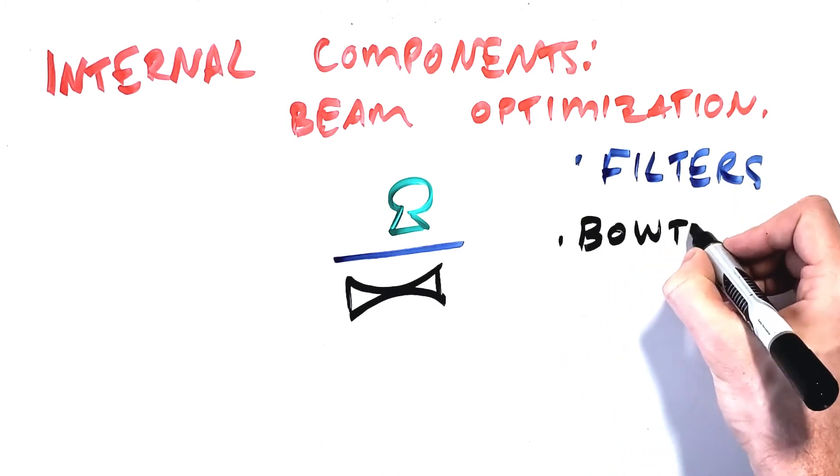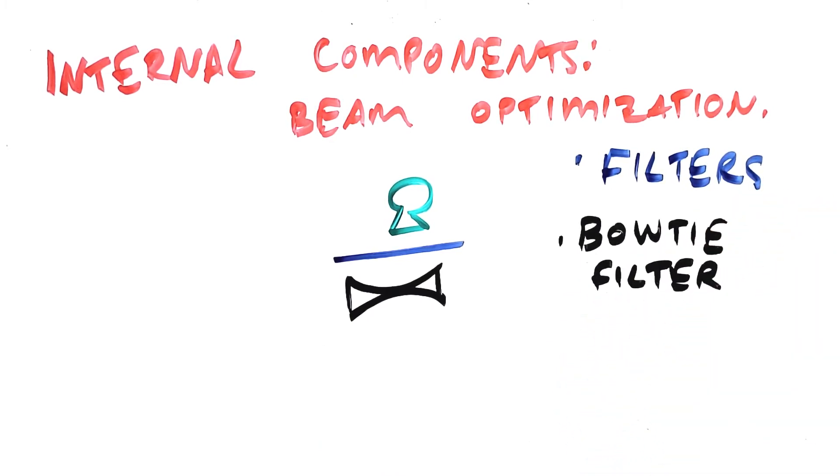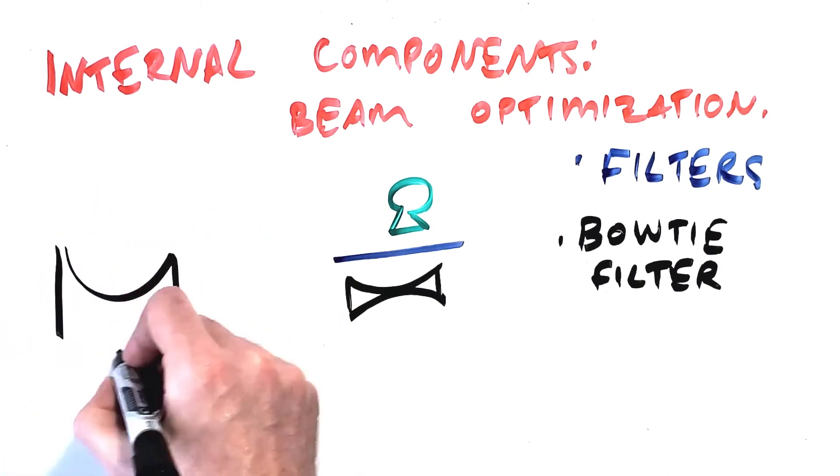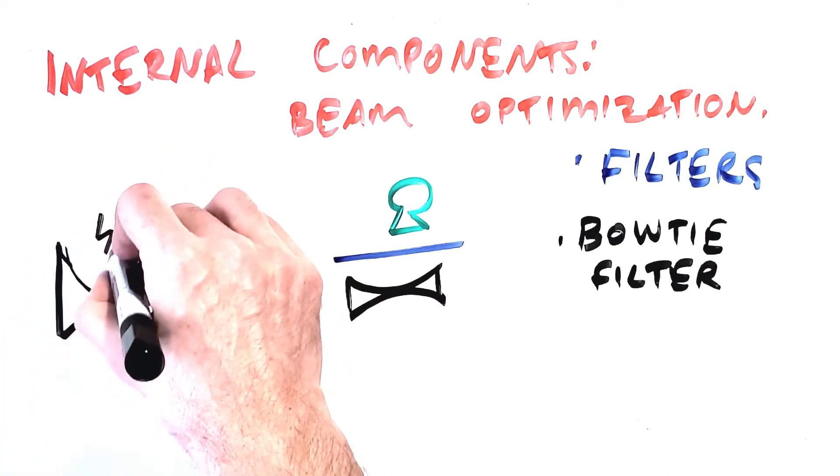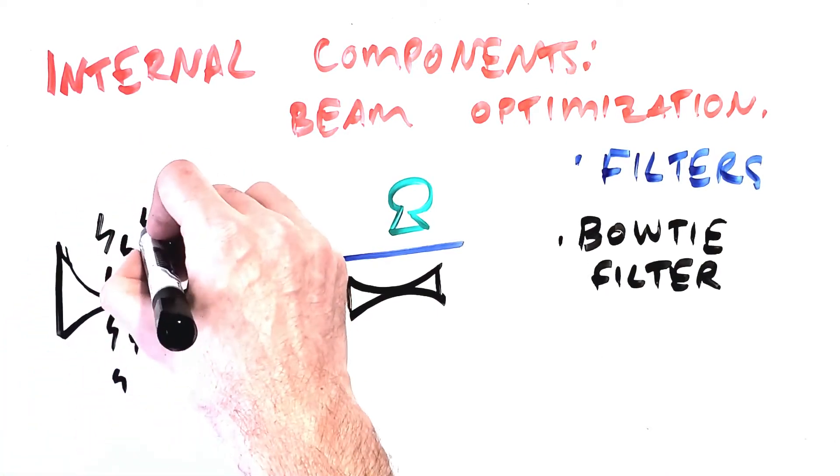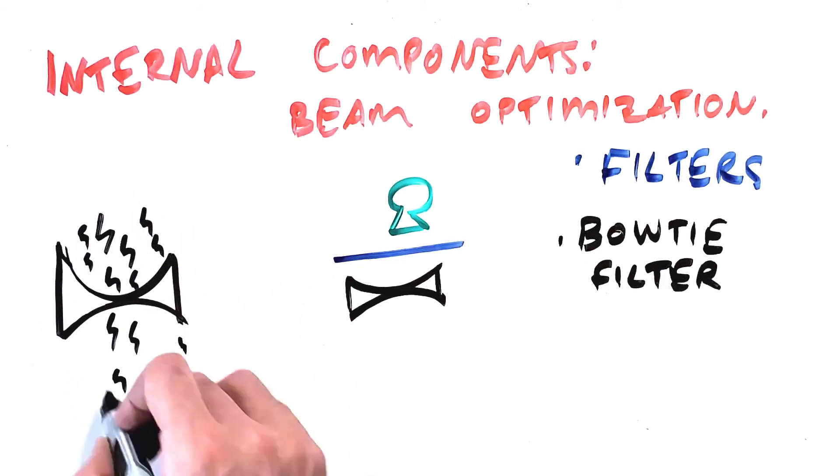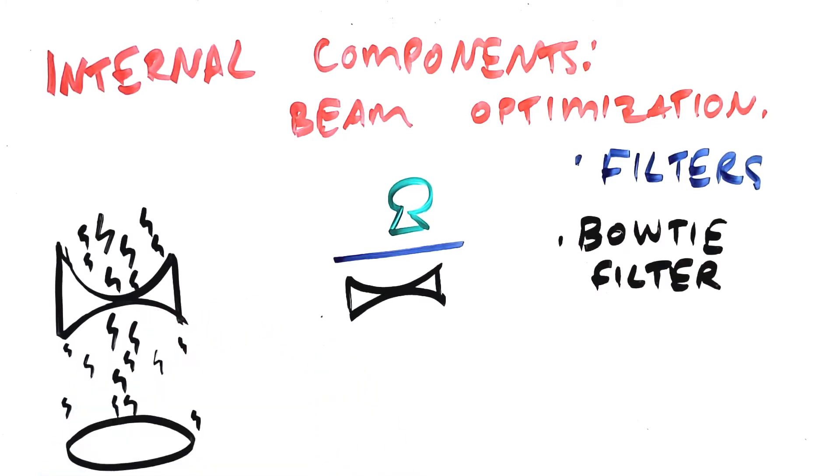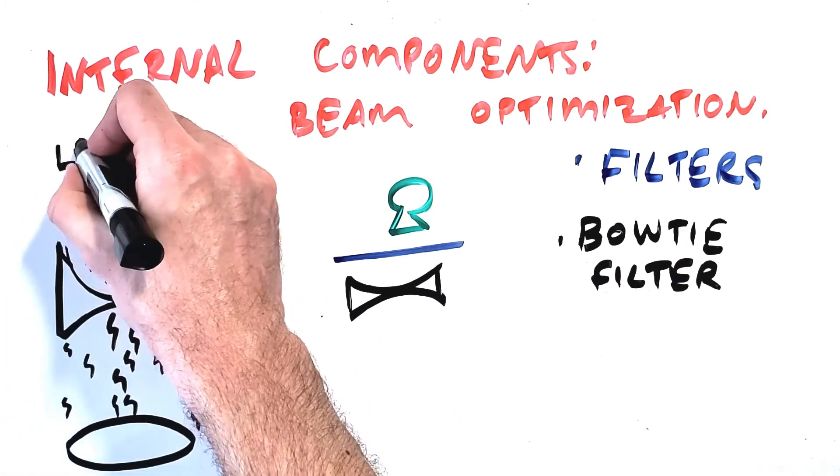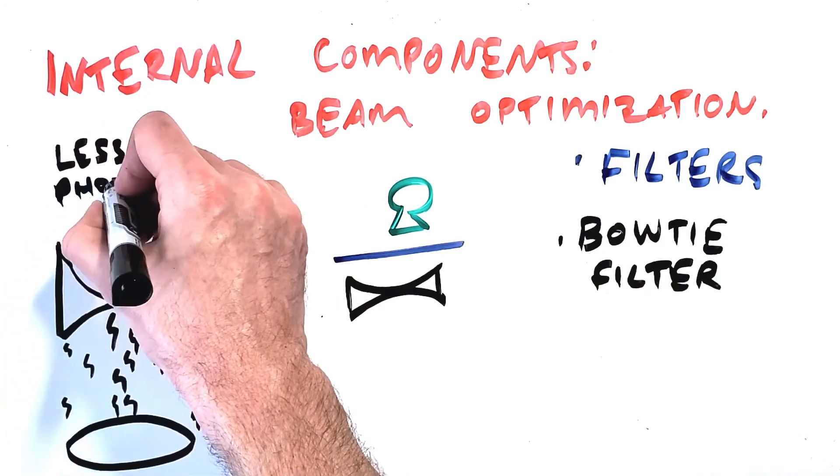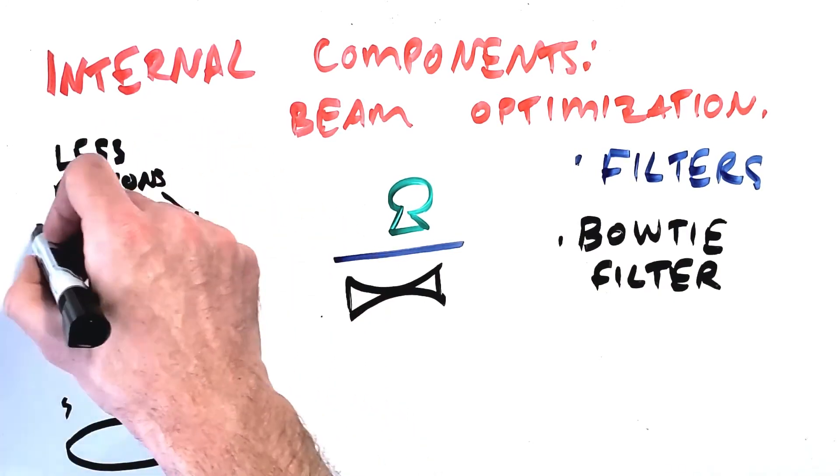And one type of filter unique to CT is the bowtie filter which is shaped like a bowtie so it's narrow in the middle and thicker at the edges. This serves to remove a higher number of photons at the edge of the patient where less photons are needed while allowing a higher number of photons to pass through the center of the patient where the additional beam penetration is required. This leads to a more homogeneous beam exiting the patient while reducing unnecessary radiation dose to the patient's periphery.